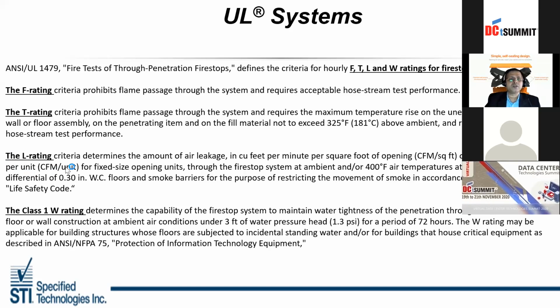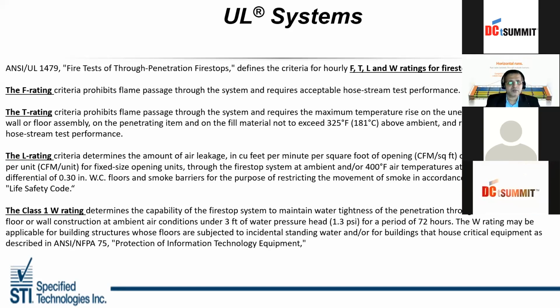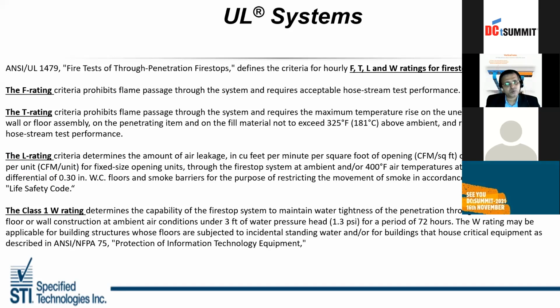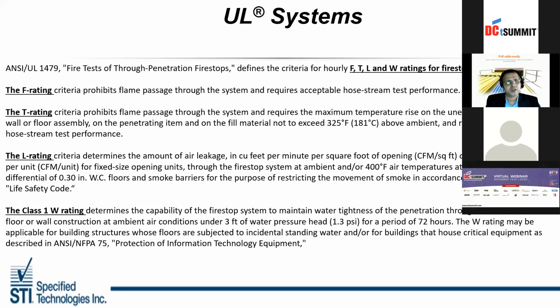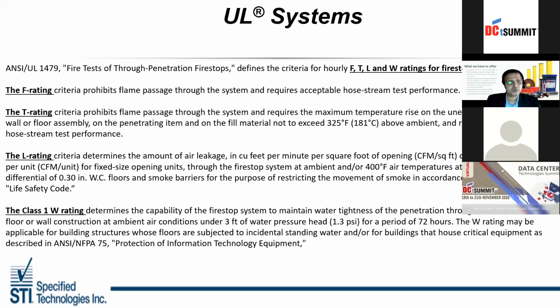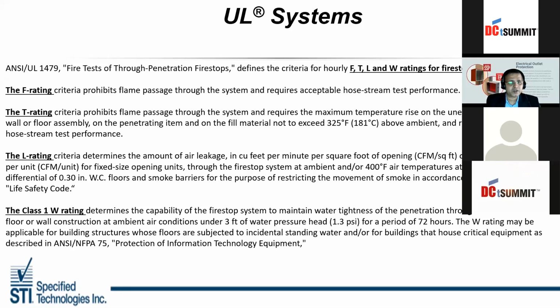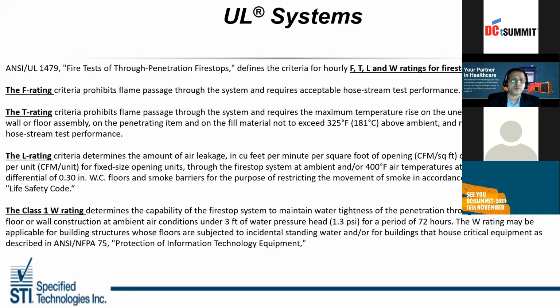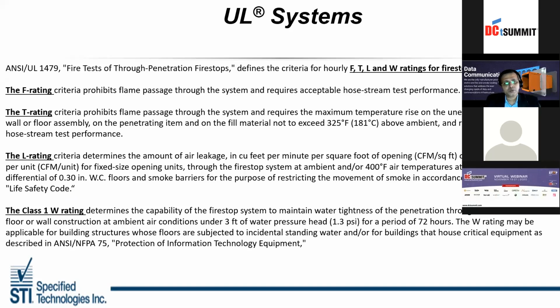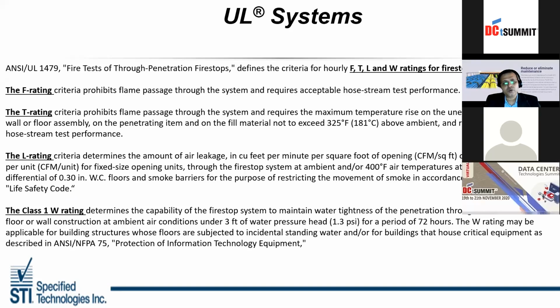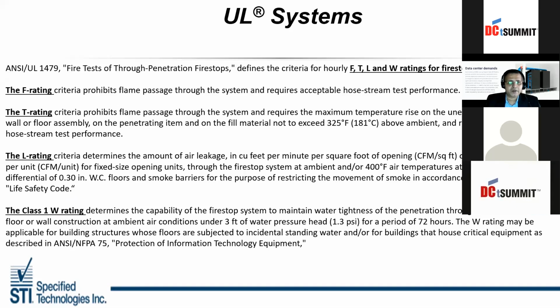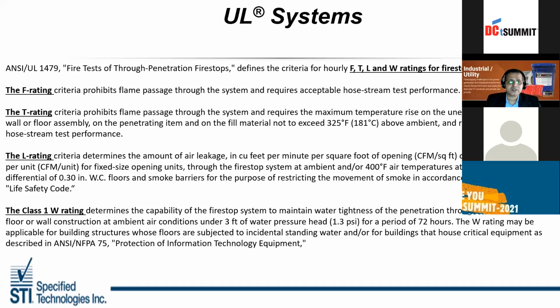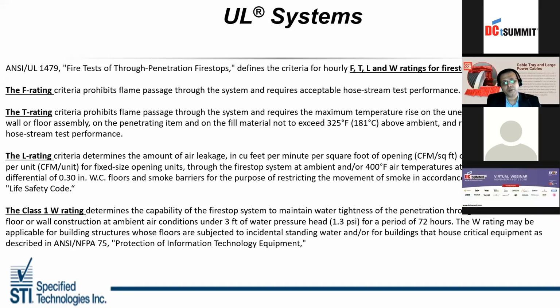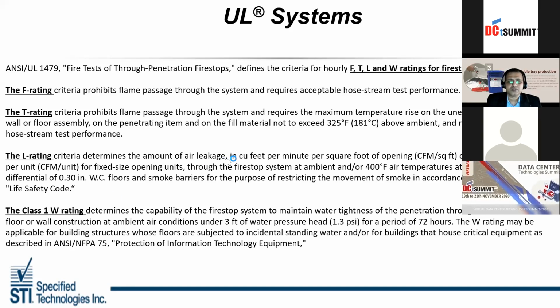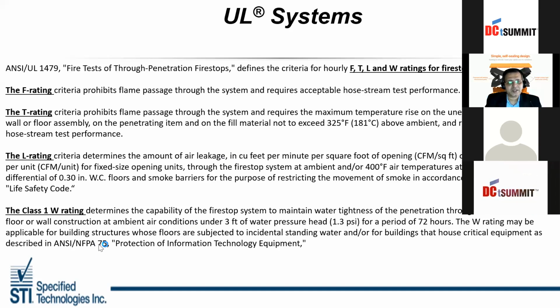Leakage rating is used wherever there are certain amounts of air leakage. There are certain requirements by the consultants where you want to define the leakage rating. Yes, we have such certifications where the L rating is also defined in those scenarios. And W rating is the water leakage rating. We don't give anything on waterproofing, but this is a leakage rating for 72 hours. Mostly we use silicone sealant in scenarios where you have a certain amount of water leakage, maybe a plumbing or firefighting pipe, and you feel that there will be water leakage tendencies. So this product, silicone sealant, will act for fire as well as the W rating, but it will not be a waterproofing product. It will be fire and water resistant up to certain hours, say 72 hours. That's it, as per the NFPA 75 standards.